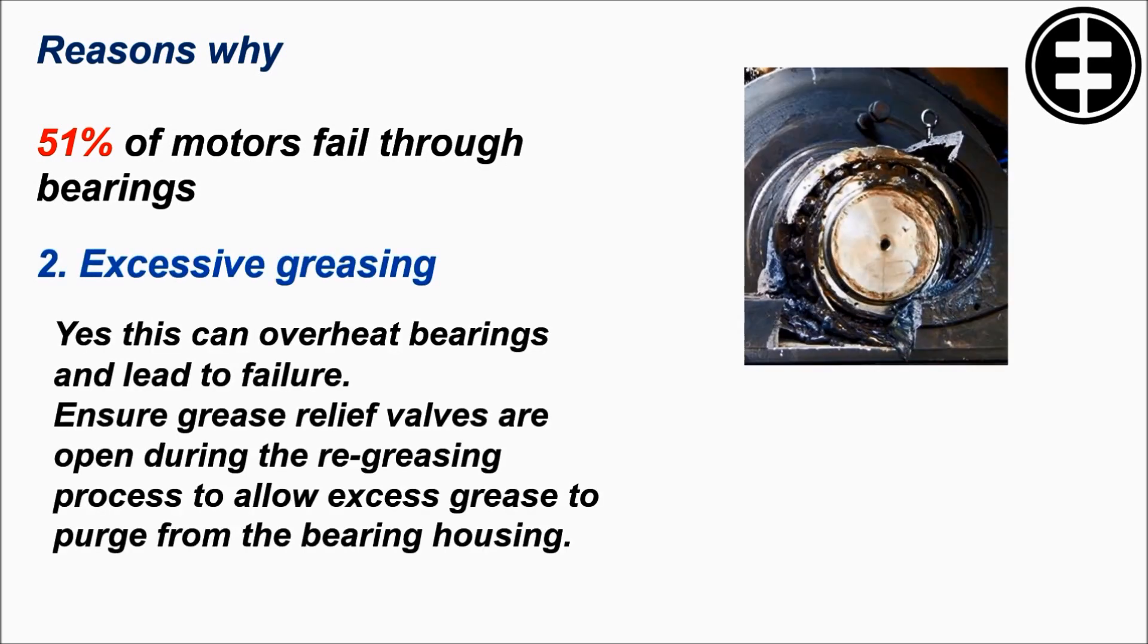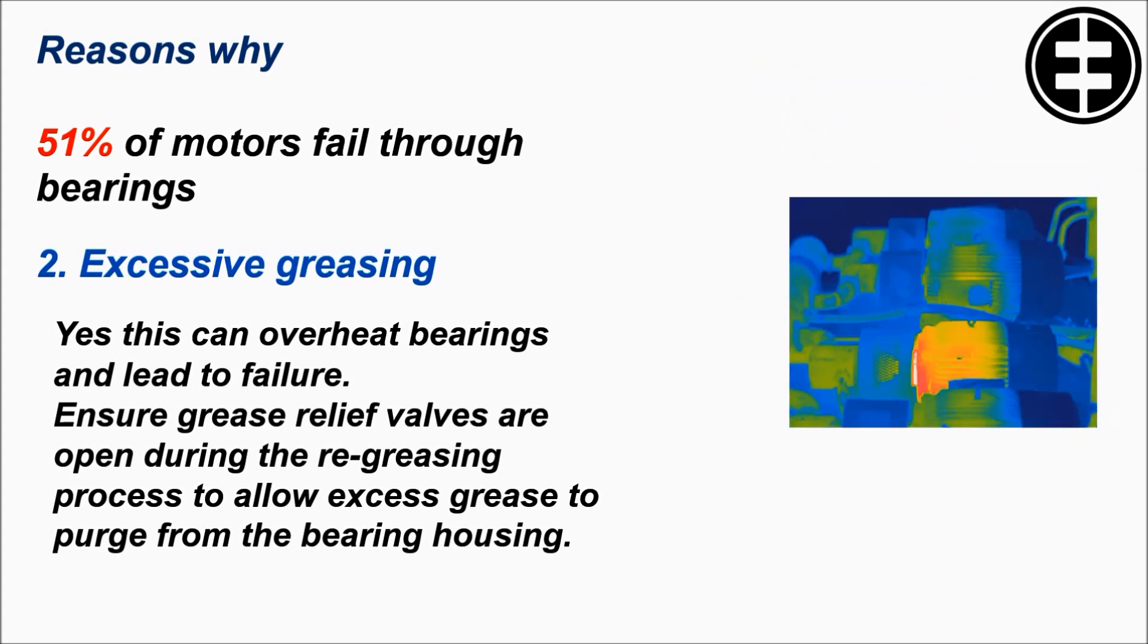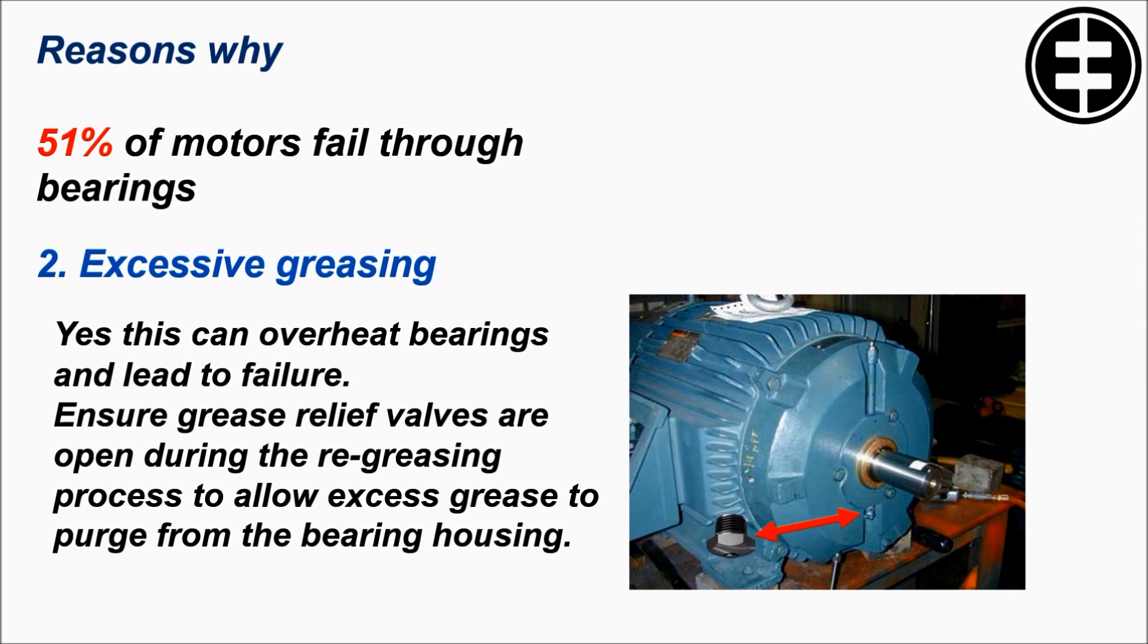Another reason why 51% of motors fail through bearings is excessive greasing. Grease is important for moving parts, but over-greasing could be a main reason for bearing failure. Yes, this can overheat bearings and lead to failure. Ensure grease relief valves are open during the re-greasing process to allow excess grease to purge from the bearing housing.